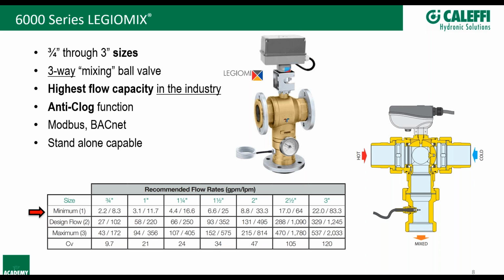Say you've got 190 gallons per minute design flow rate in a building. Our design flow rates are based on a 7.5 psi drop. We've got our minimum flow rates, our design flow rates at a 7.5 psi drop, and maximum flow rates at a 20 psi drop. So you always want to get as close to the design flow rate as possible. You've got 190 as your design. A 1.5 inch is designed at 93, 2 inches at 131, but then you make a big jump up to 2.5 inches, which is 288.